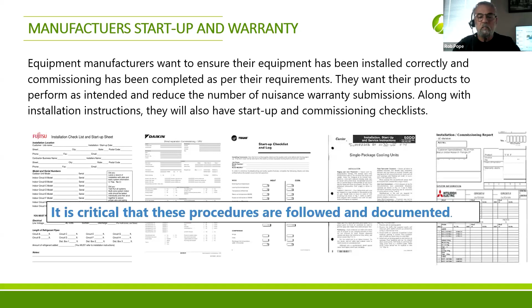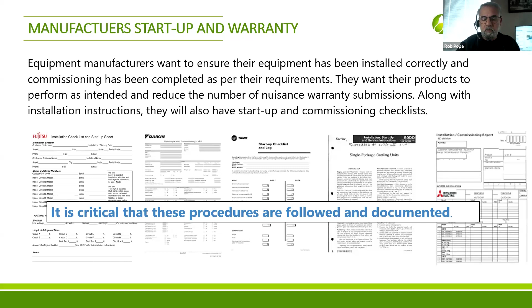So here's an example. All the manufacturers have these commissioning checklists, in every manual for every major piece of equipment. I'll emphasize over and over again that it really is important that all this paperwork is done—each of these parts of the commissioning, and this is only one part of it, is followed, filled out, and recorded. So this is the startup checklist.